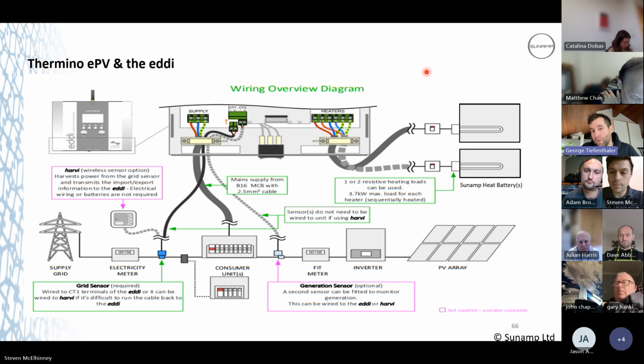How are you designing that, if you see what I mean? Because the customer wants the water they want, so you've got to deliver them 15 litres a minute at 40 degrees. What's the purpose of having those 2 batteries? It gives you somewhere else to put your spare PV if you've got any. Is that the sole reason for it? That's the sole reason, if the customer wants to.